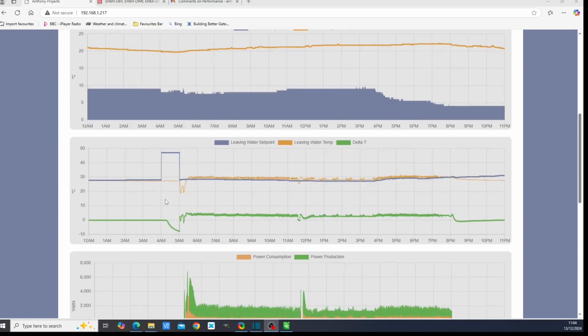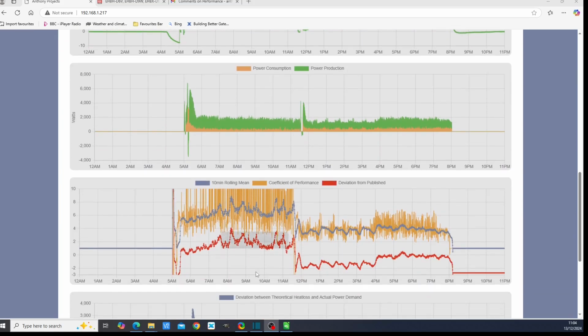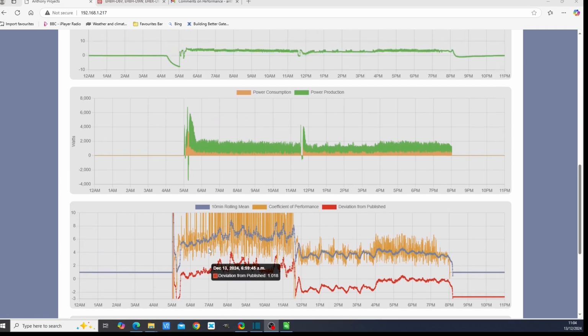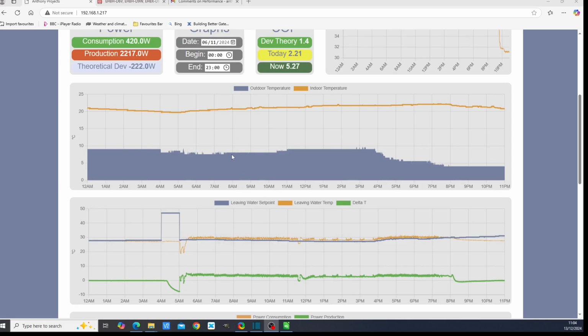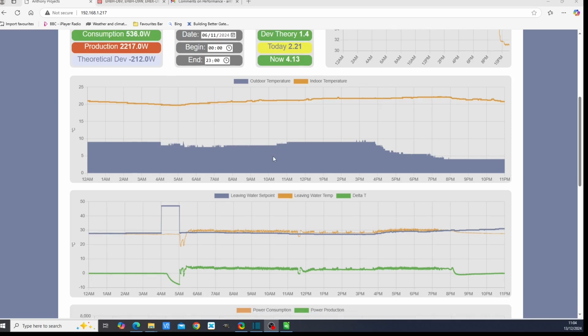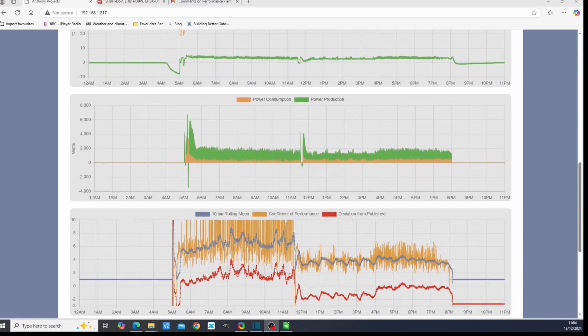Well, here, if we scroll down, we have got two different performance regimes happening. If we go back up here, you can see that the temperature has been fairly consistent throughout the whole day. It's been about 8 degrees, rising up to 9 degrees in the afternoon. So not a particularly varied day, but in between the good and the bad performance regime, the heat pump switched off for a brief period of time.